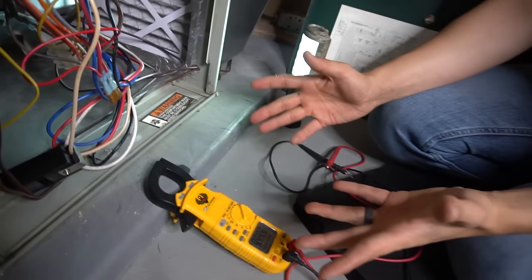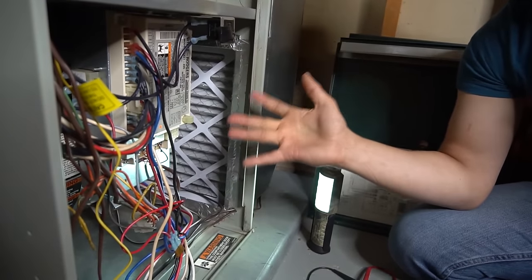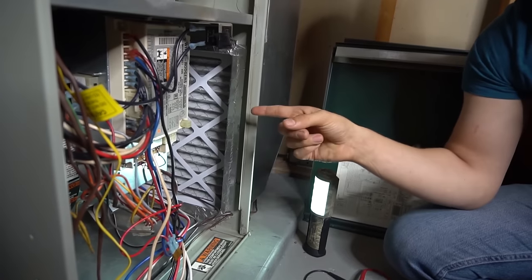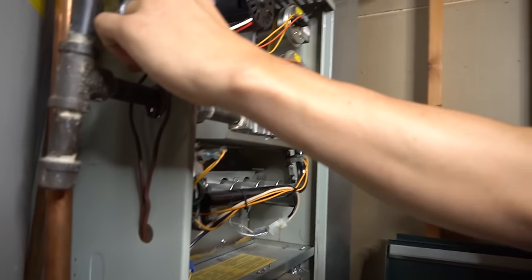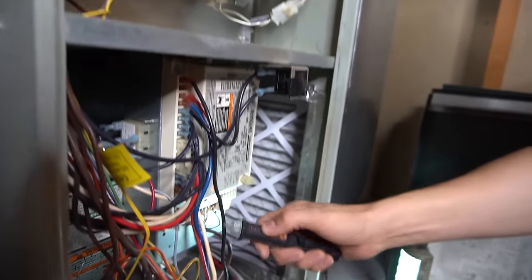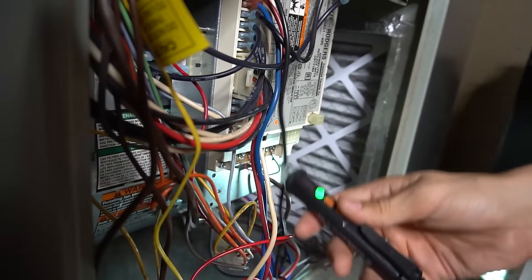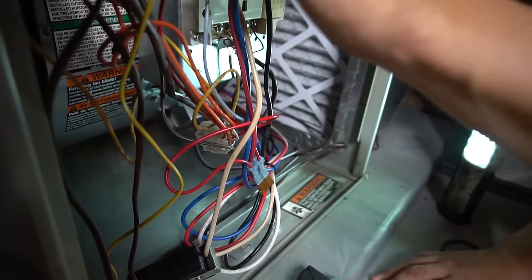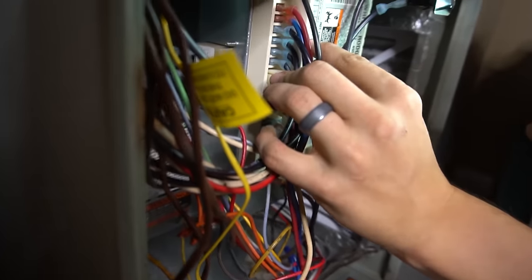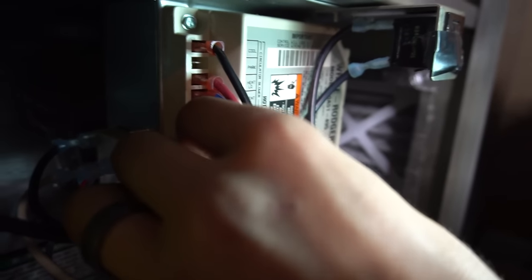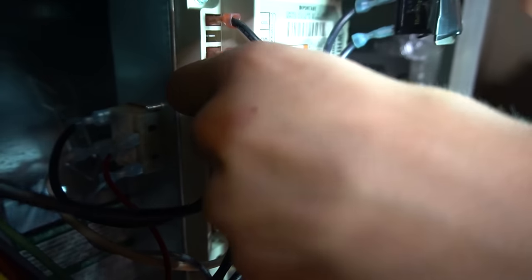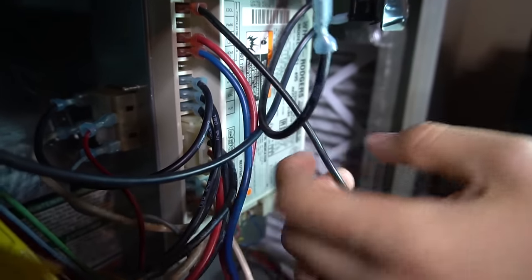Now, if you don't have a meter and you can't check if your blower motor is getting voltage or not, one way you could try testing it is to hotwire it directly. So for example, you turn your power switch off. You don't want to have any power. Confirm with the voltage pen or meter that you don't have any voltage anywhere. And I don't. And then what you want to do is find your line terminal where the power comes into the control board. You want to pull that wire off. So in my case, it'll be this one right here. It'll usually be coming from the door switch. Pull that wire off.